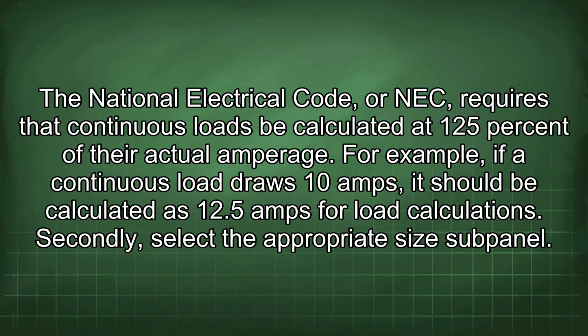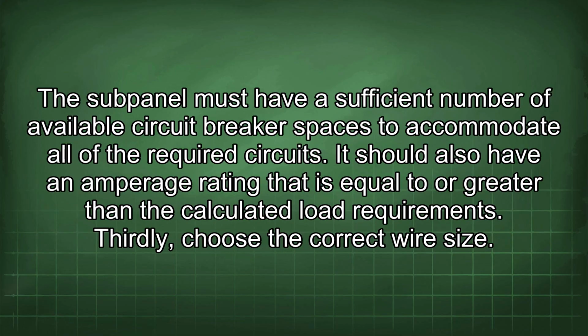The National Electrical Code, or NEC, requires that continuous loads be calculated at 125% of their actual amperage. For example, if a continuous load draws 10 amps, it should be calculated as 12.5 amps for load calculations. Secondly, select the appropriate size subpanel. The subpanel must have a sufficient number of available circuit breaker spaces to accommodate all of the required circuits. It should also have an amperage rating that is equal to or greater than the calculated load requirement.